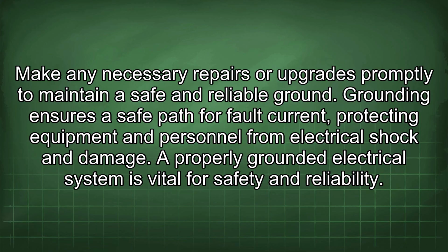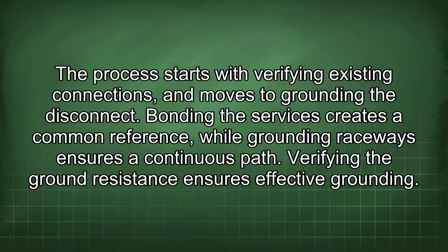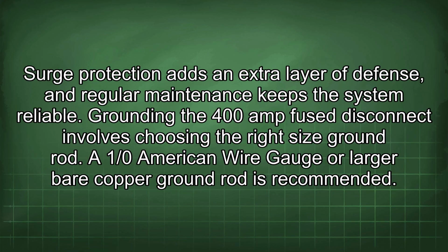Grounding ensures a safe path for fault current, protecting equipment and personnel from electrical shock and damage. A properly grounded electrical system is vital for safety and reliability. The process starts with verifying existing connections and moves to grounding the disconnect. Bonding the services creates a common reference, while grounding raceways ensures a continuous path. Verifying the ground resistance ensures effective grounding. Surge protection adds an extra layer of defense, and regular maintenance keeps the system reliable.